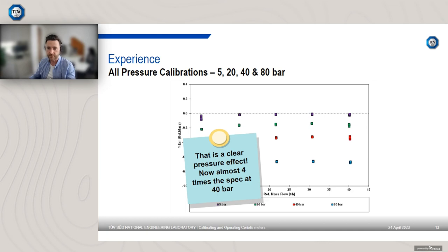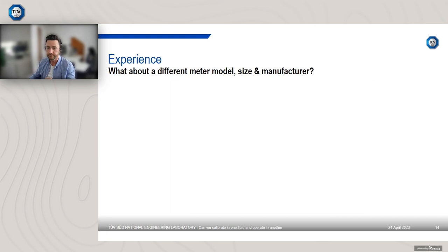Now we can see there's a clear pressure effect, and we're almost 4 times the specification at 40-bar. So at 40-bar we're underreading by 0.4%, so that's 4 times that 0.1% specification. So that's just one meter type.